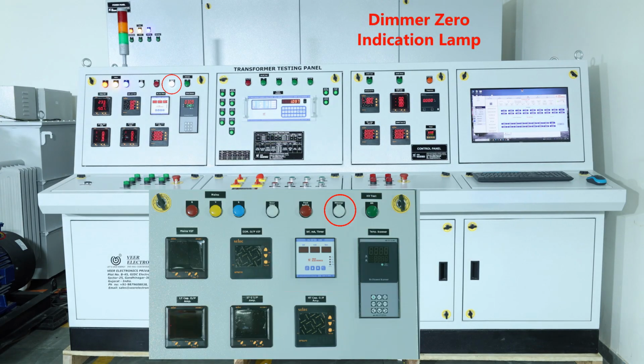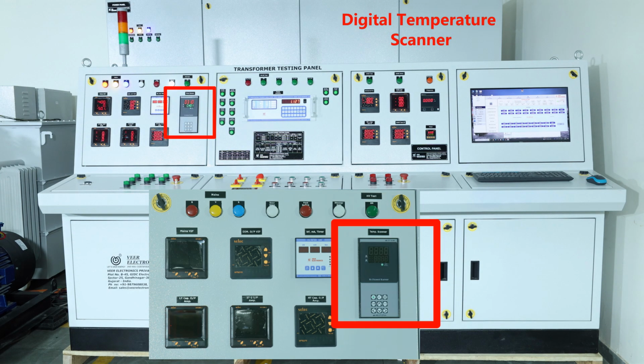This is the dimmer zero indication lamp. This is the HV test on indication lamp. This is the 16-channel digital temperature scanner. Here, we provide 16 PT100 temperature scanner inputs along with a meter. It measures the temperature of various parts of the transformer during the temperature rise test.